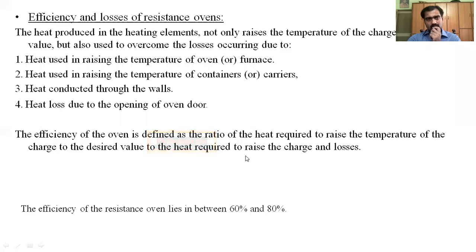When three phase supply is available, we place three electrodes to heat the charge. As an example, in resistance ovens operated between temperature ranges of up to 1050 degrees centigrade and 1350 degrees centigrade — for medium temperature furnaces, the range is 300 to 1050 degrees centigrade. For hardening metals, very high operating temperatures are required, and those are high temperature furnaces operating above 1050 degrees centigrade. Efficiency of these ovens is about 60 to 80 percent.